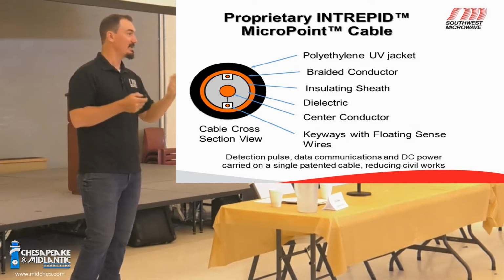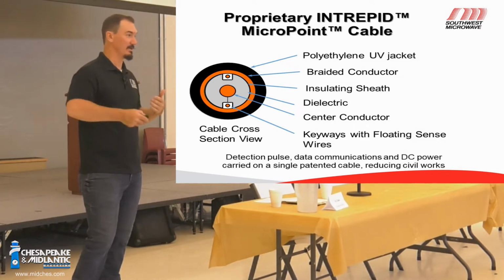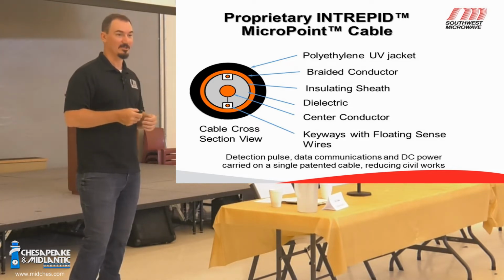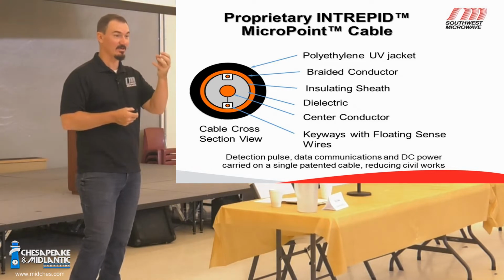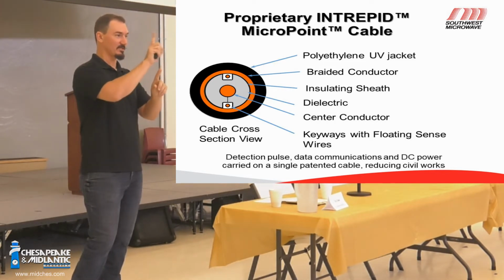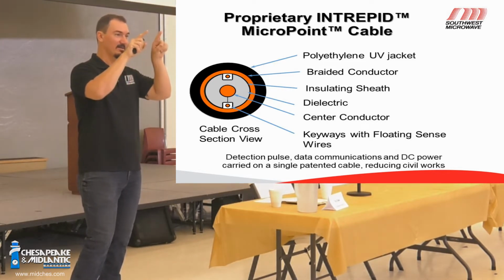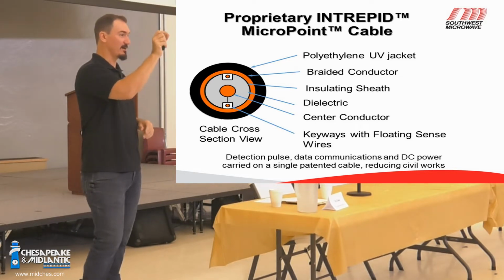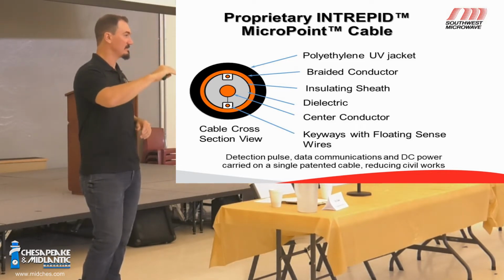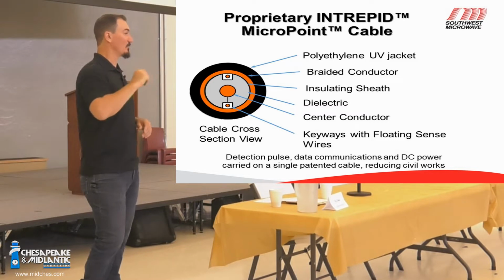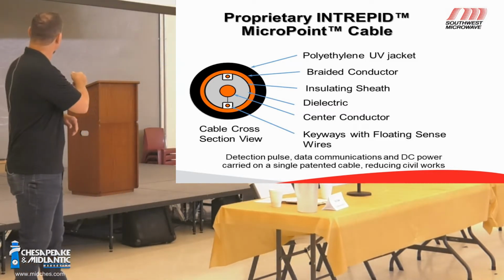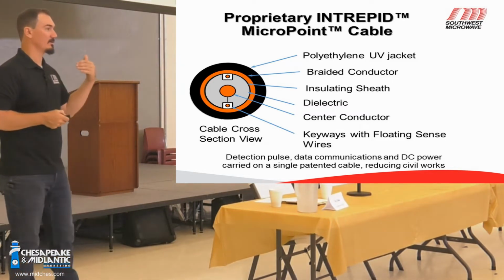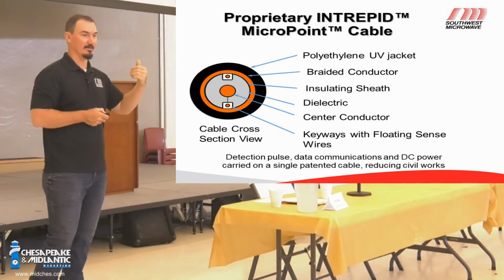So this is something that anybody should be able to check and view and do a spot check. You should walk out there and there should be dielectric grease. So where the sensor cable comes up and the 2 little sensor wires are out of it, dielectric grease should be from there all the way down the braid, all the way until it hits the outer jacket.